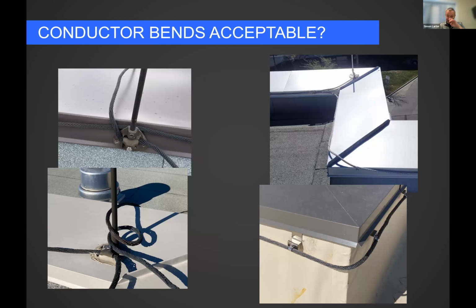Are the conductor bends acceptable? Well, on the left-hand side, not particularly. I don't think I need to tell you that looping the conductor around a lightning rod a couple of times isn't a valid connection. That one, ladies and gents, is another roofer special. I'll show you a few more roofer specials before we're done here, but that one's a particularly egregious case of the roofer not knowing what to do with the lightning protection. Oh, I'll just loop it up here, that'll hold it in place. That's not really how it's done, folks.